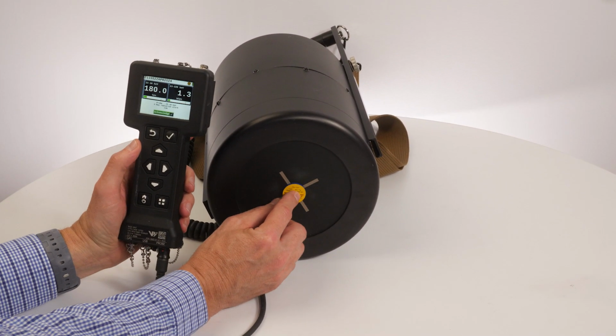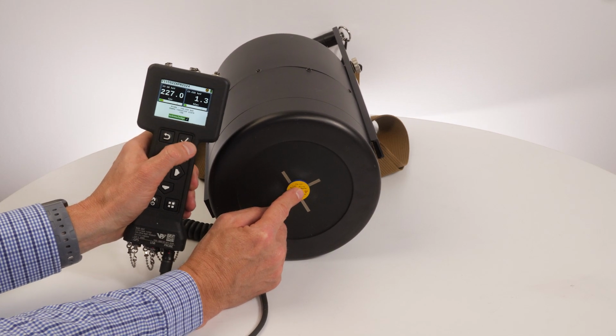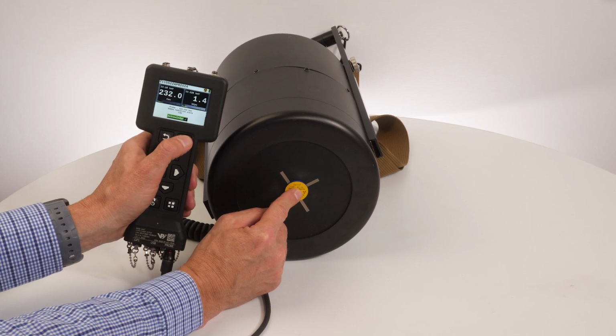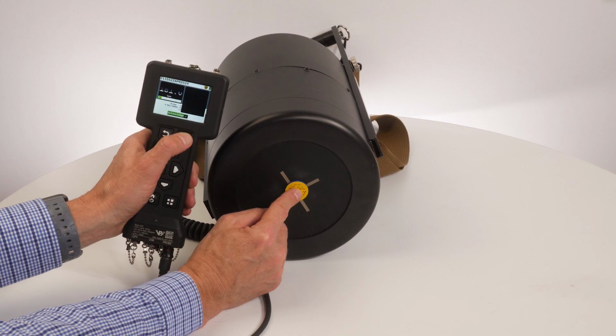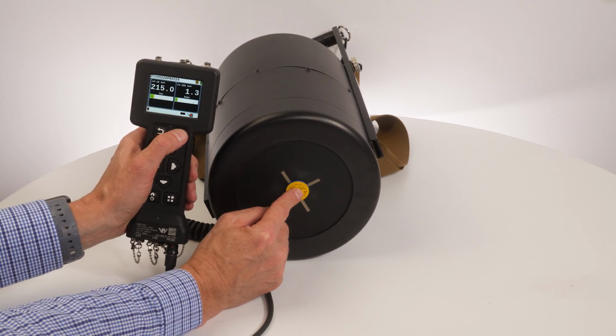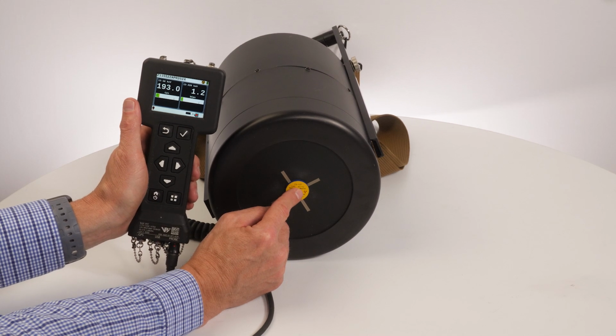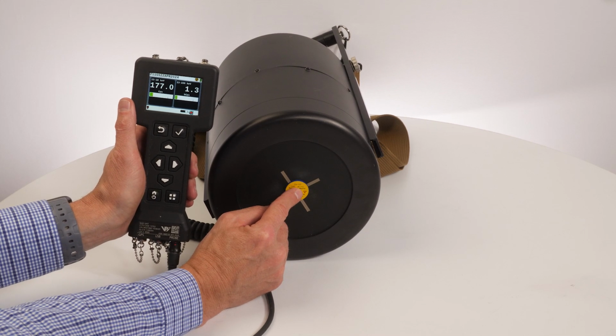If the alarm thresholds are set at a level that causes a radiation alarm, acknowledge any alarms by pressing the Enter key. There may be alarms in more than one channel, requiring multiple acknowledgements. Hold the check source in place for at least 30 seconds, allowing the reading to settle.